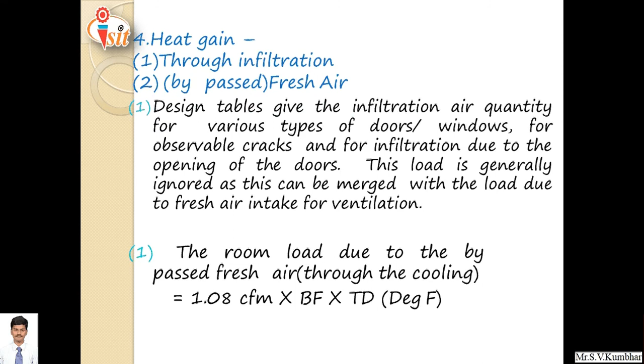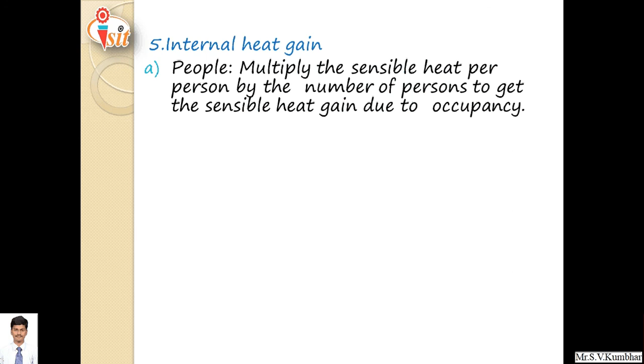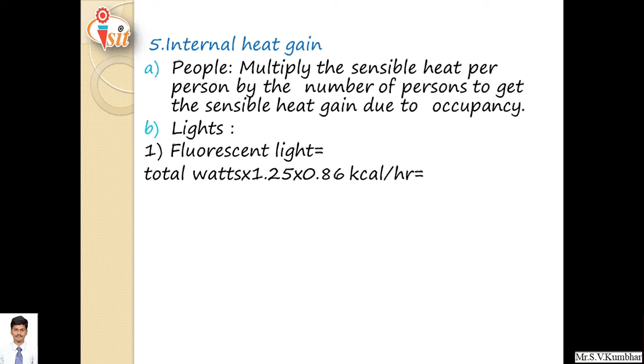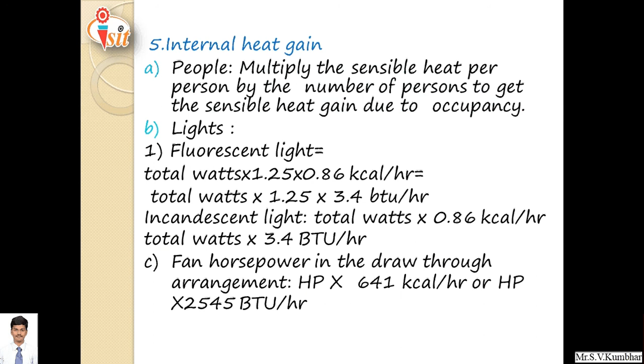Internal heat gain. First, people: multiply the sensible heat per person by the number of persons to get the sensible heat gain due to occupancy. Second, lights: for fluorescent light, it is equal to the total watts of fluorescent light multiplied by 1.25 multiplied by 0.86, which gives us the internal heat gain. Third, fan horsepower in the draw-through arrangement, which is equal to HP into 641 kilocalorie per hour, or HP into 2545 British thermal units per hour.